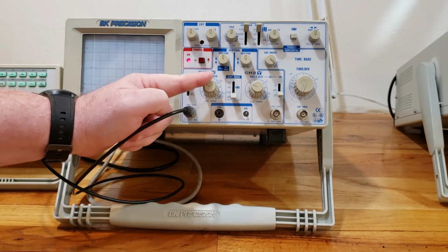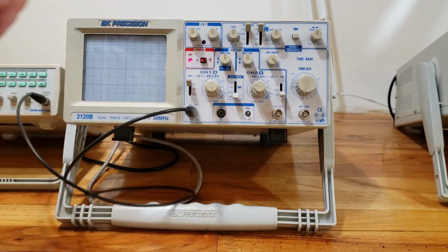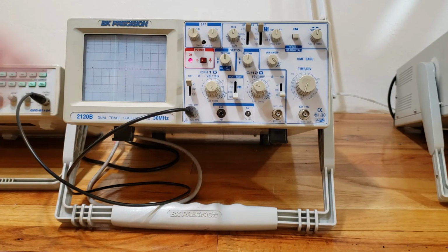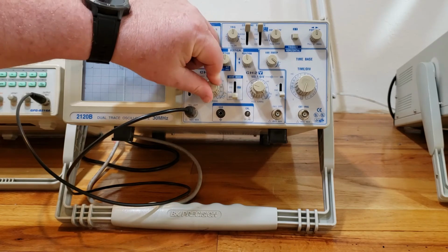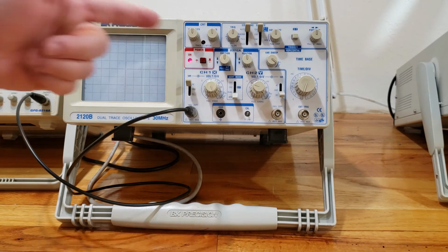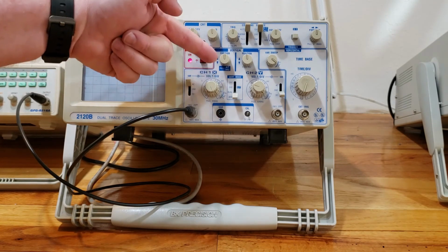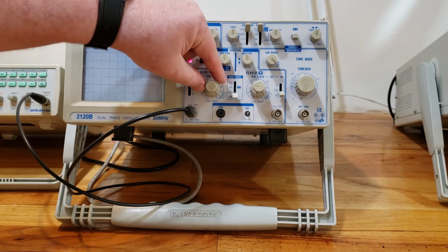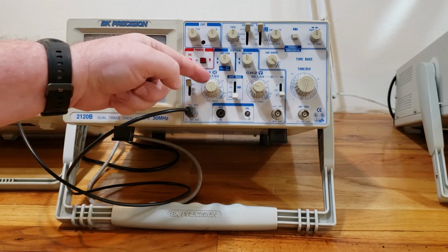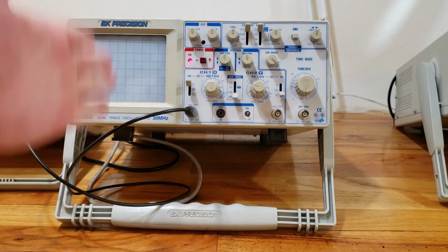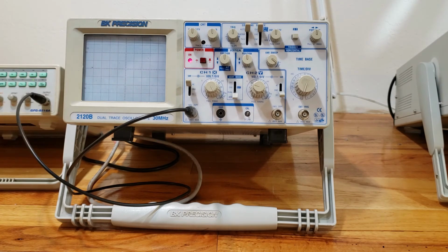Now, the volt division knob, there are actually 3 things that I'm going to do to this. The first thing is I'm going to make sure that the top part is pushed in. The second thing is to make sure that the top part is locked into position all the way to the right, and you'll hear it when it locks into position. The next thing is the actual volt division part of the knob, this big part of the knob right here. I'm going to adjust that so that it's pointing at 0.2 volts right now. That way it's almost centered.